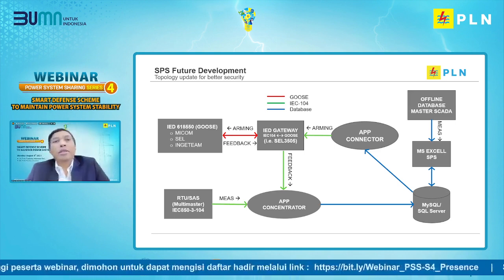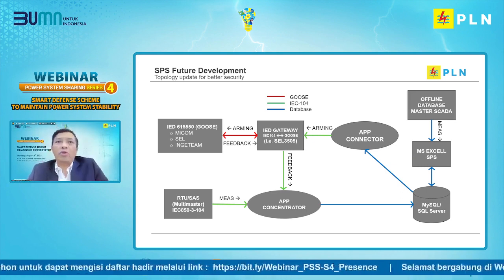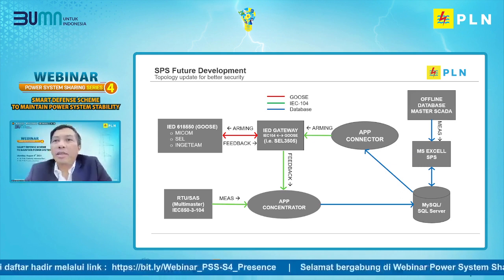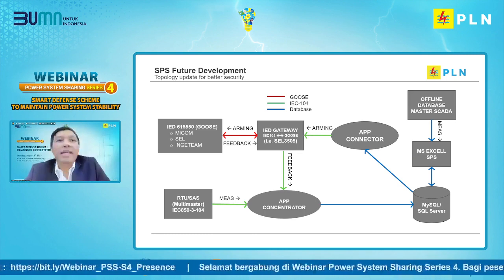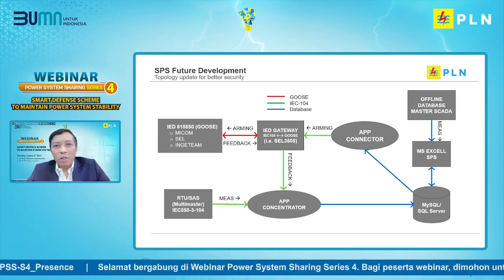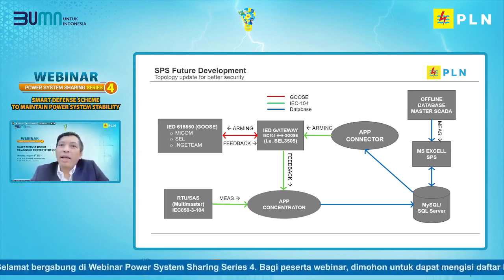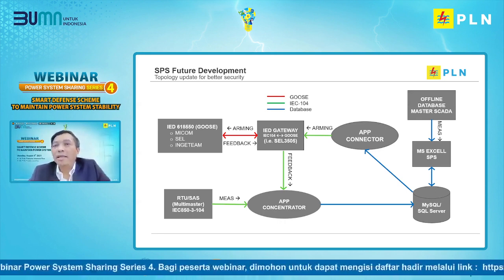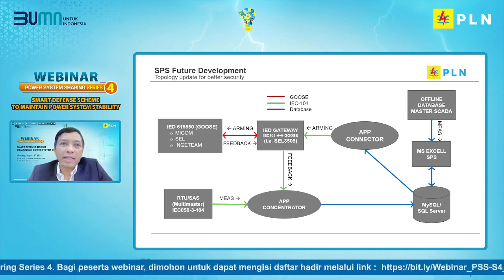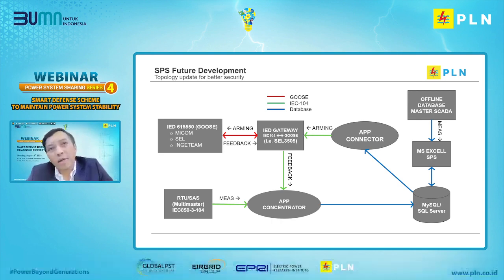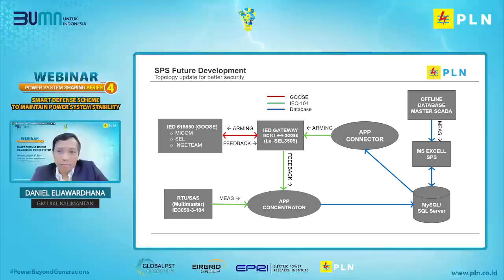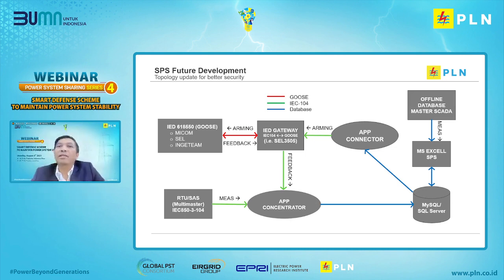this graph shows the SPS topology for the development plan. The previous topology of the communication between the server and the SPS hardware in the subsystem used a shared database, the existing condition. In order to improve cyber security, the communication line between the server, IED, Intelligent Electronic Devices, and SPS relays will use the standard protocols IEC 61850 and IEC 60870-5-104. In addition, the SPS server can also acquire data directly from RTU SAS with this new topology. We are currently in the process of procuring servers and supporting equipment to improve the cyber security of the system.